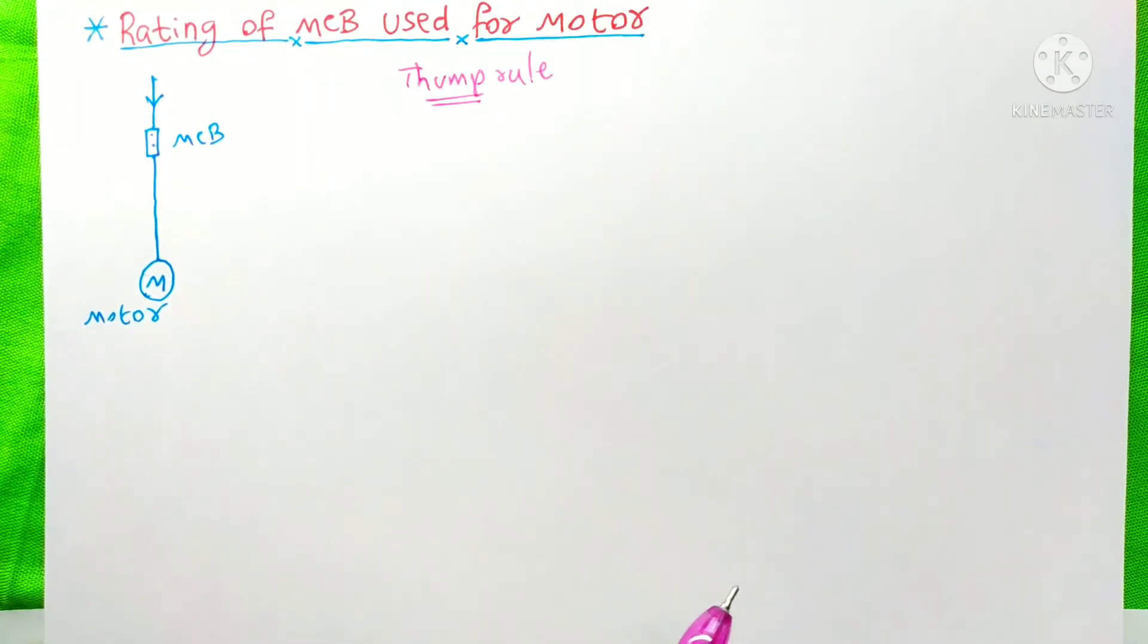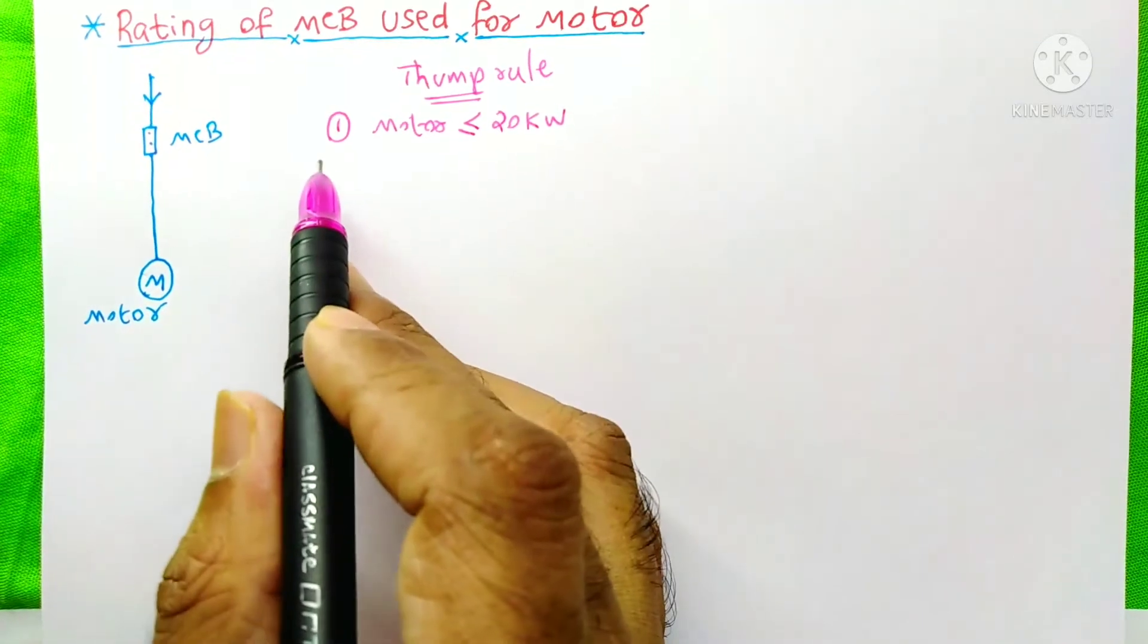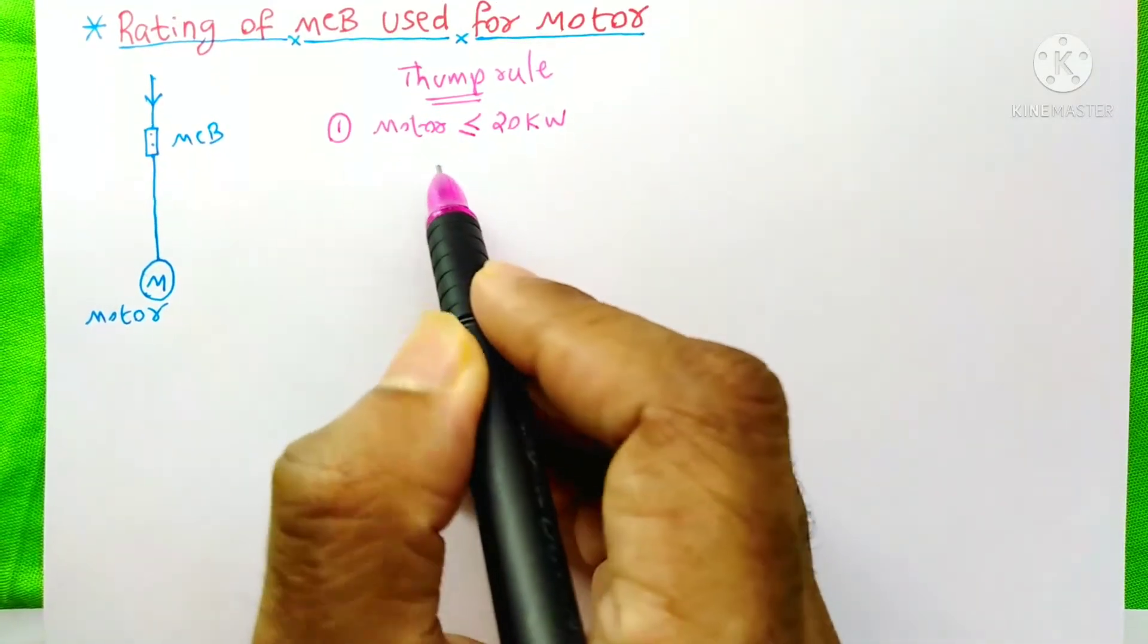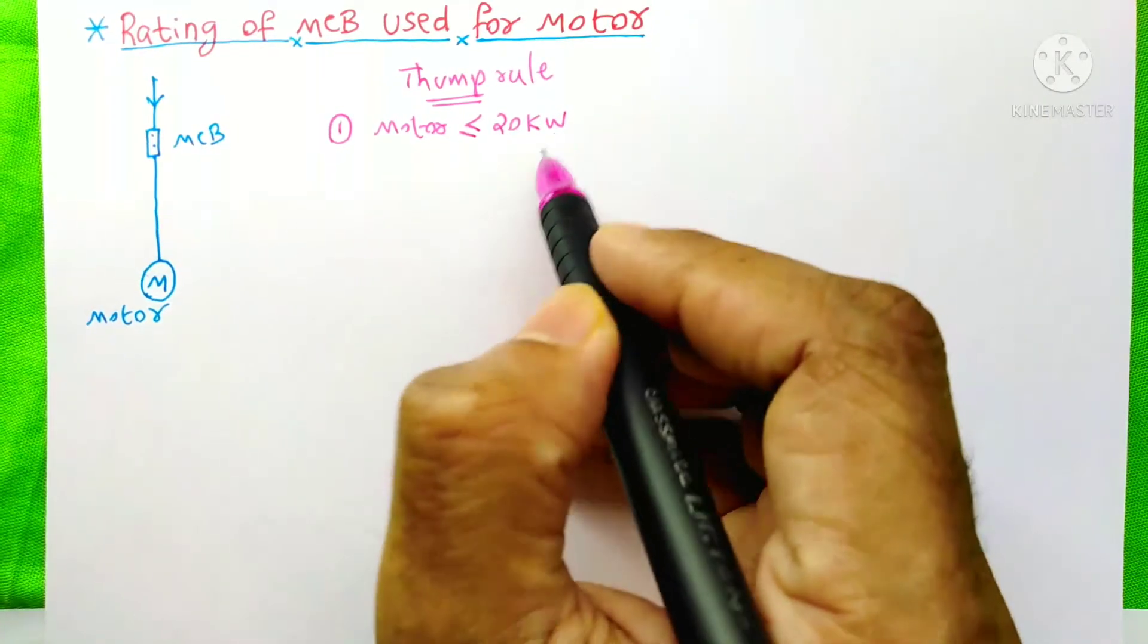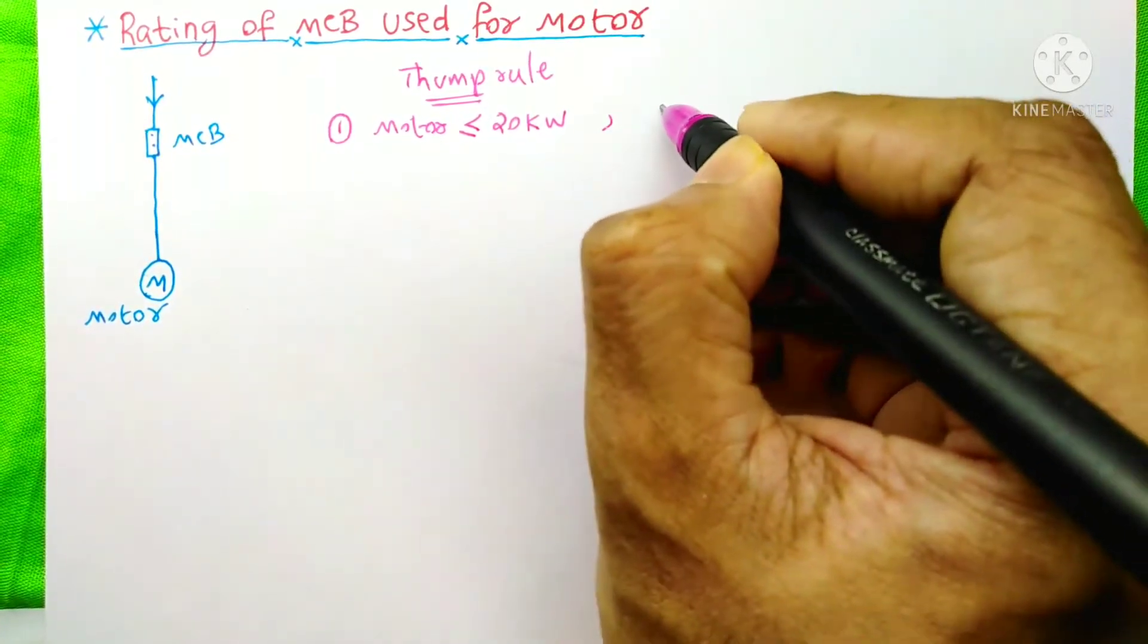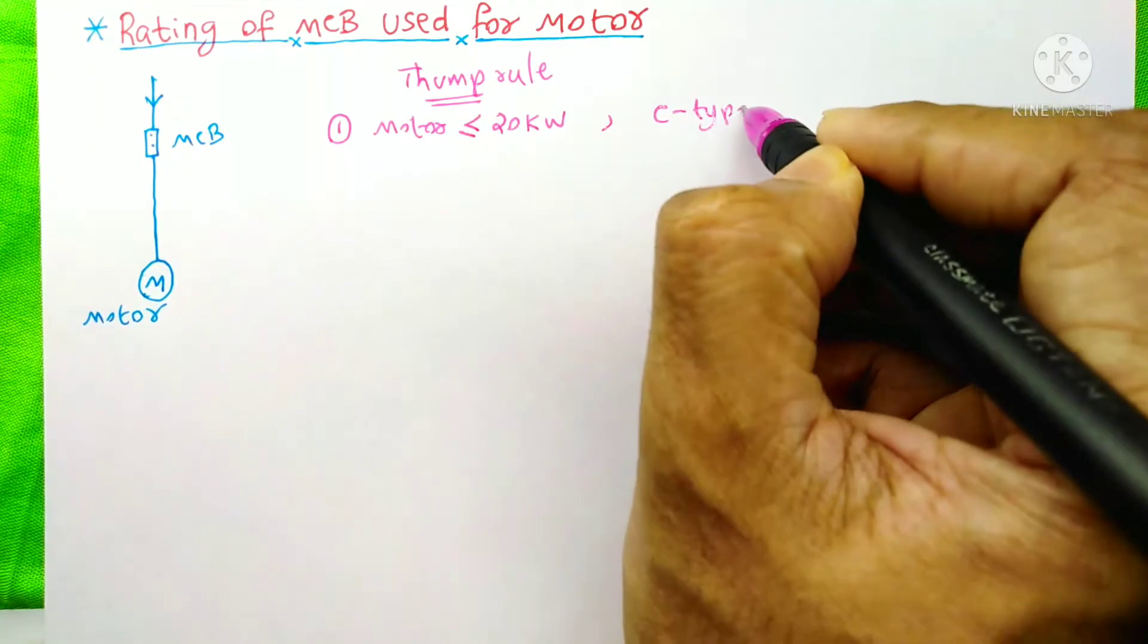I am an electrical engineer. To learn about this, please don't skip this video till its last. Thumb rule number 1 is if your motor's capacity is less than or equal to 20kW, then you must choose the C-type MCB.